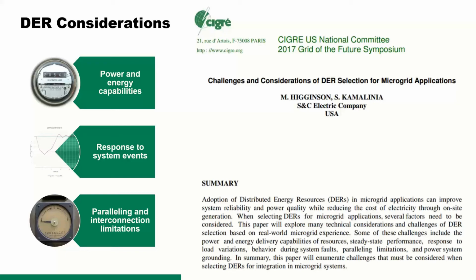The last one is a very important one because paralleling and interconnection limitations need to be considered as part of the DER selection, since the system needs to function through different use cases, where DERs may need to be able to connect or disconnect from the grid when they get control commands.